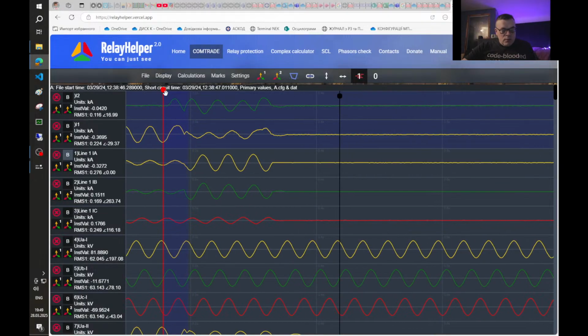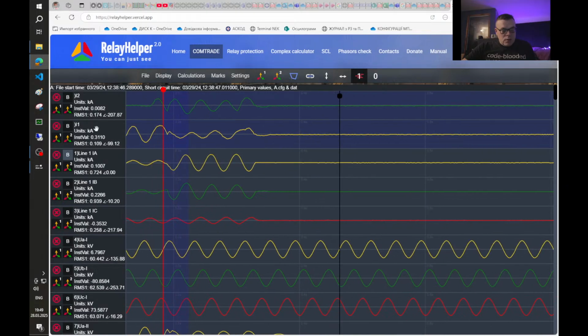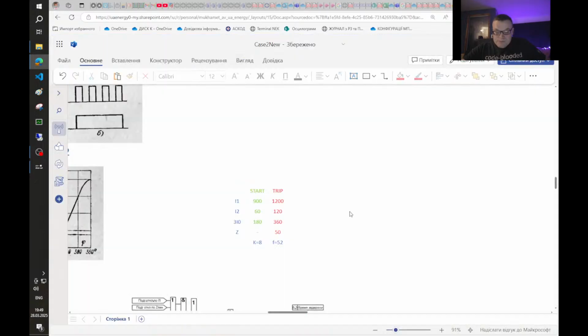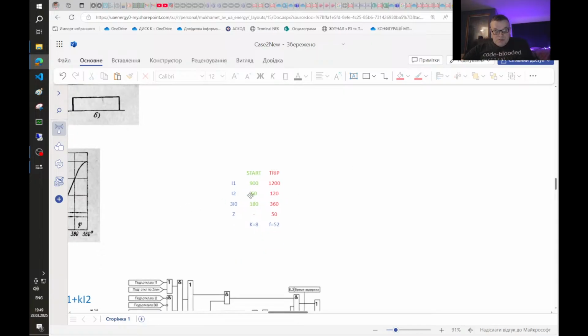A little bit more, and almost 165 amperes. So let's check our settings. Yes, so I believe that this channel initiated the starting of the protection and also the trip. So the current was big enough to initiate start and trip.